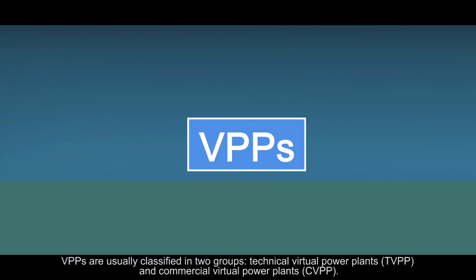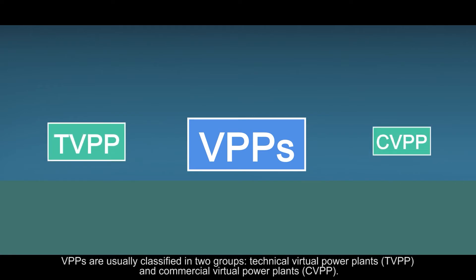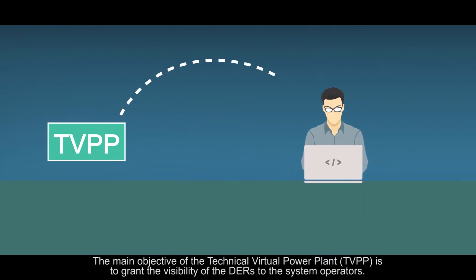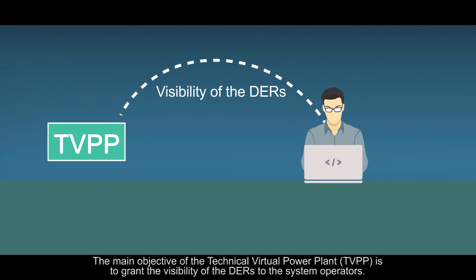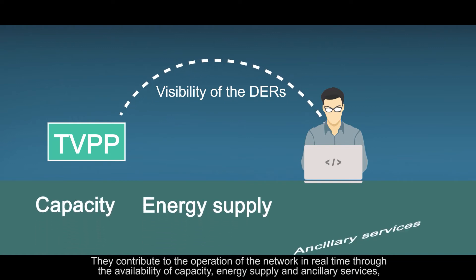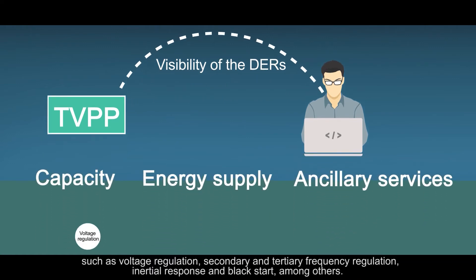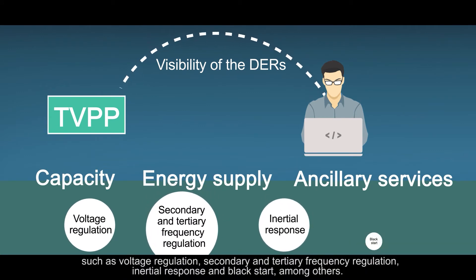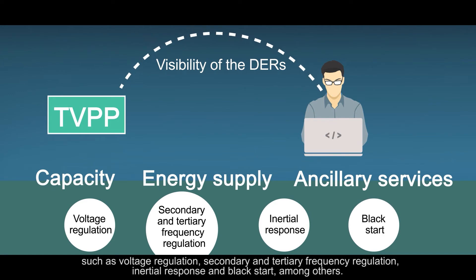Virtual power plants are usually classified in two groups: technical virtual power plants and commercial virtual power plants. The main objective of the technical virtual power plant is to grant the visibility of the distributed energy resources to the system operators. They contribute to the operation of the network in real time through the availability of capacity, energy supply and ancillary services, such as voltage regulation, secondary and tertiary frequency regulation, inertial response and black start, among others.